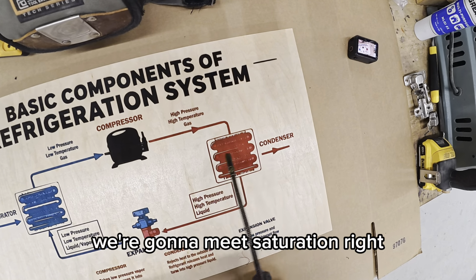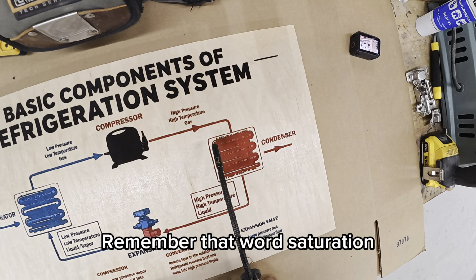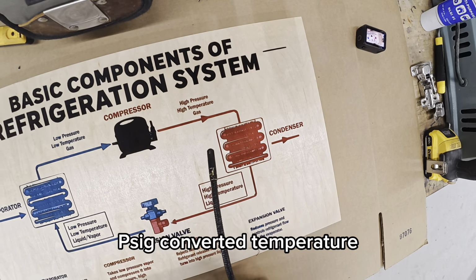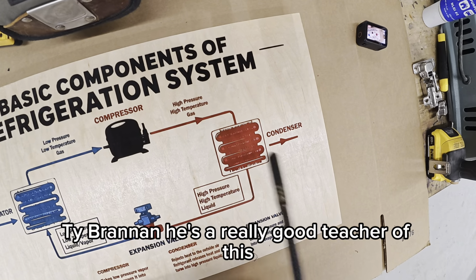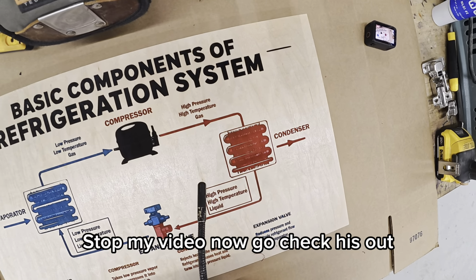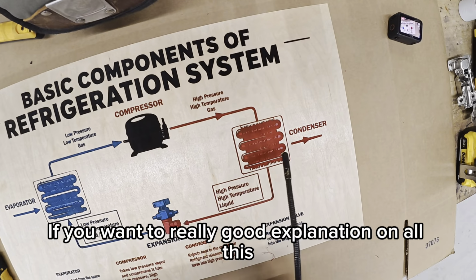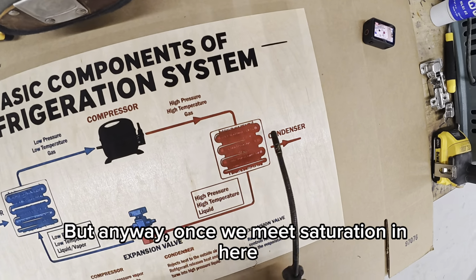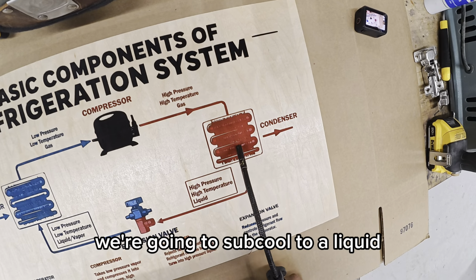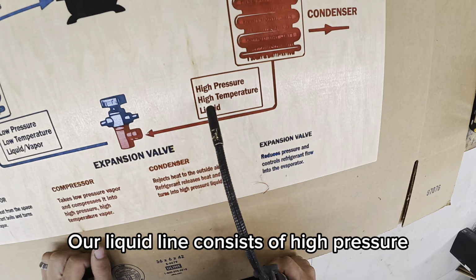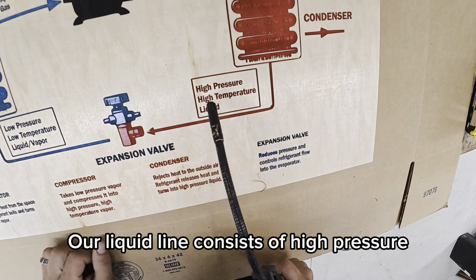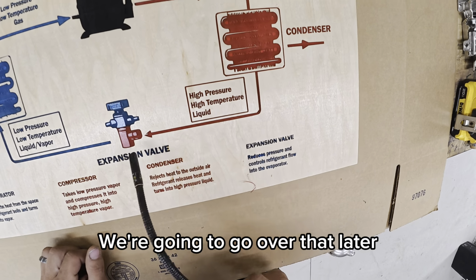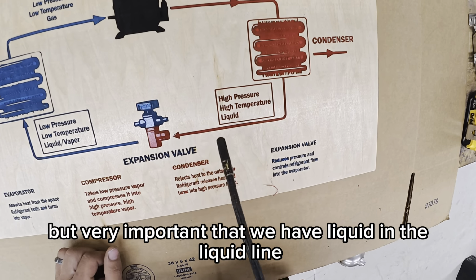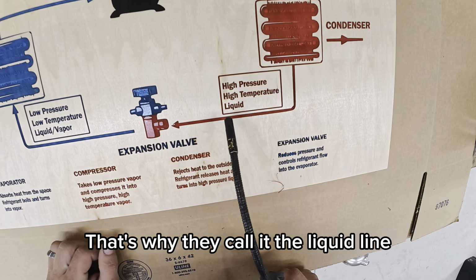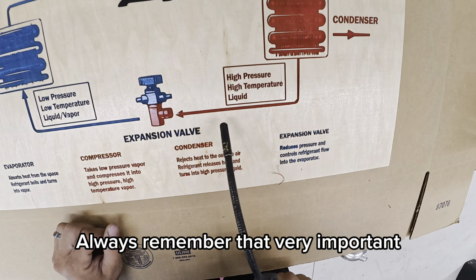We're going to meet saturation, right? Remember that word, saturation. PSIG, converted temperature. Ty Branneman, he's a really good teacher of this. Stop my video now, go check his out if you want to. Really good explanation on all this. But anyway, once we meet saturation in here, we're going to subcool to a liquid, and then we're going to go to our liquid line. Consists of high pressure, high temperature liquid. We have to have liquid in this line. That's very important. We're going to go over that later, but very important that we have liquid in the liquid line. That's why they call it the liquid line. Always remember that, very important.